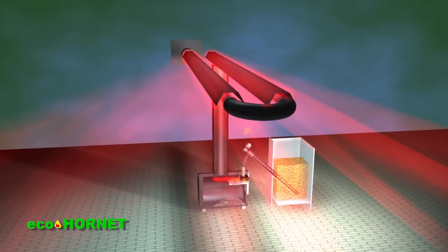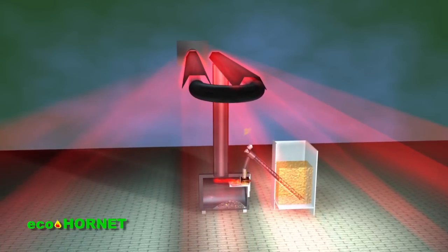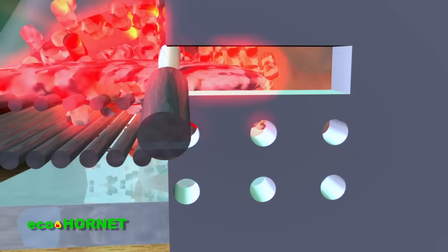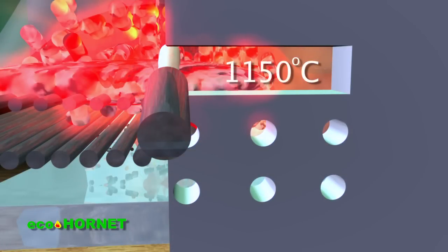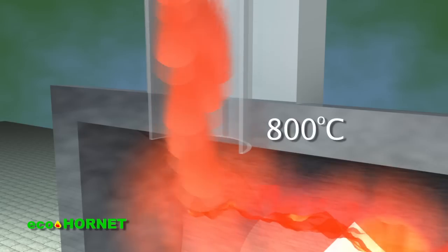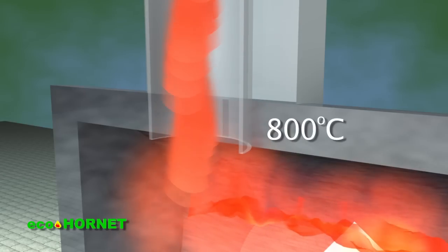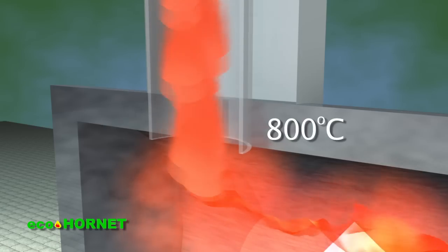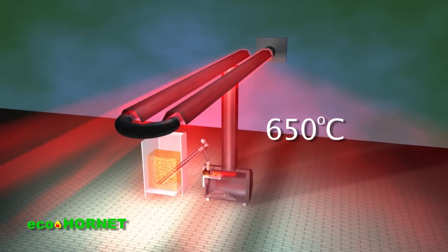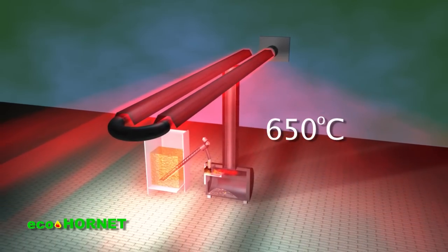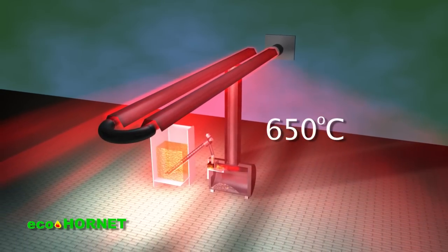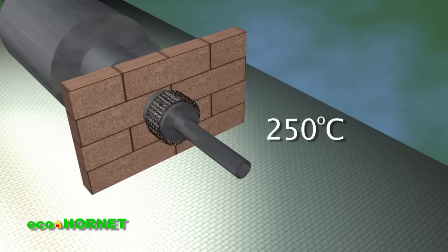The pellet combustion temperature of 1000 to 1150 degrees Celsius is reduced by dosing secondary air and upon entry of the burnt gases into the insulated routing tube, their temperature does not exceed 800 degrees Celsius. Upon reaching the radiant tube it is 650 degrees Celsius and it reaches no more than 250 degrees Celsius at the level of the exhaust system.